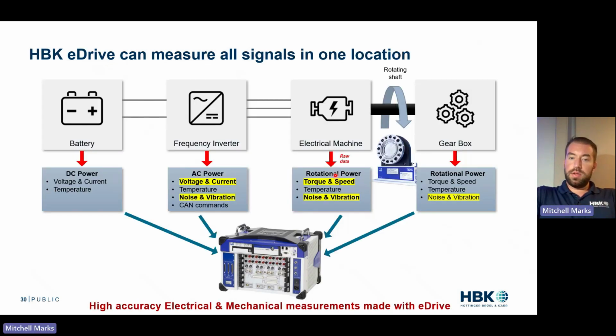All right, the eDrive system can measure all of these different signals, AC voltage and current, noise, vibration, CAN bus, all into one measurement unit. And we can do lots of them. You can also bring your high accuracy, high speed torque in. So you can see voltage, current, torque, noise, accelerometer, microphone, all time aligned, so you can have that confidence. You can go to that FFT, you can go to that cycle-based tracking.